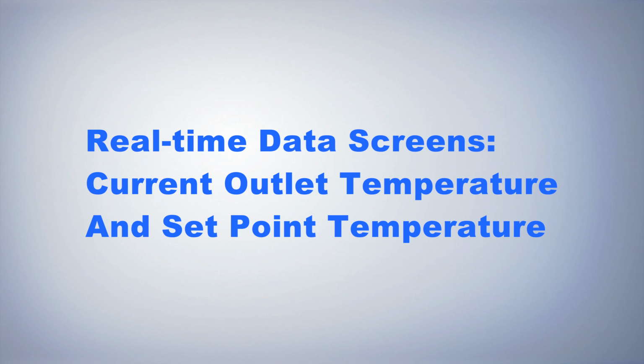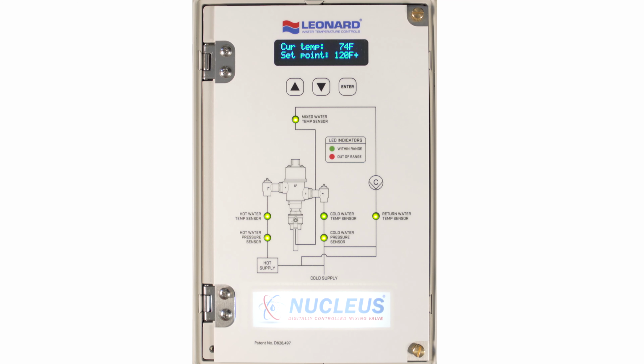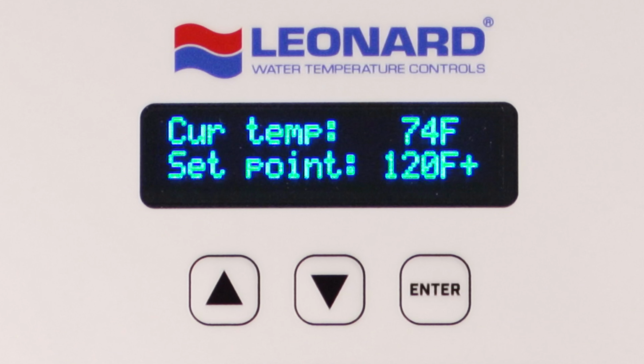Real-time data screens. Current outlet temperature and set point temperature. On the home screen and after the initial full sweep, the digital display indicates the current measured temperature on the mixed outlet of the valve, T3, and shows the set point temperature on the line below. Note: a large negative value displayed at the current temp line indicates the sensor is damaged or not properly wired to the main control board.